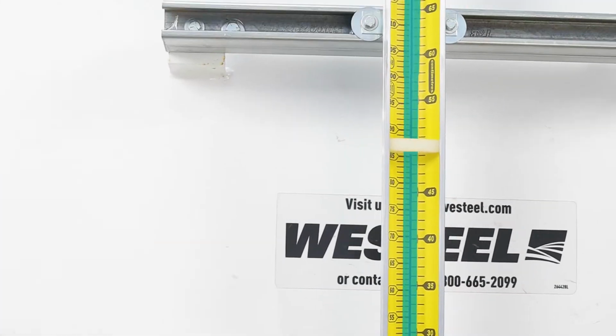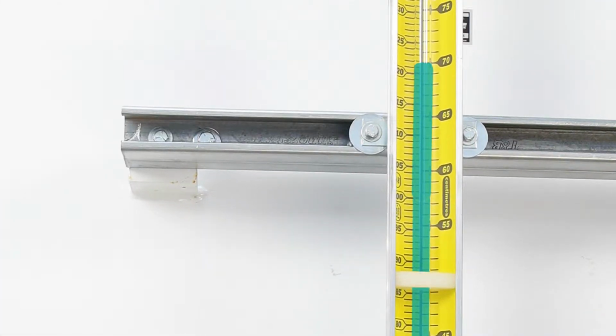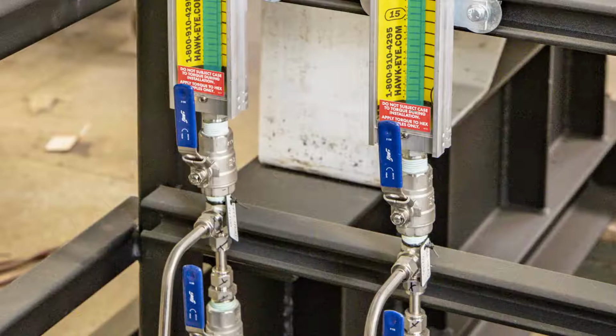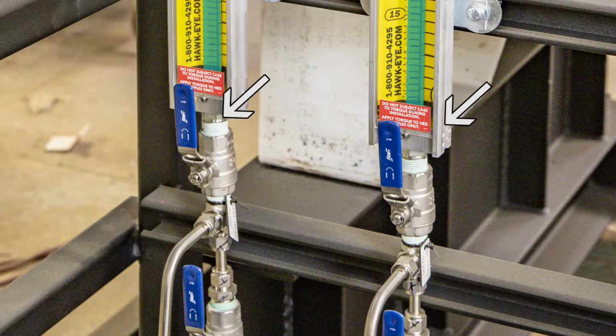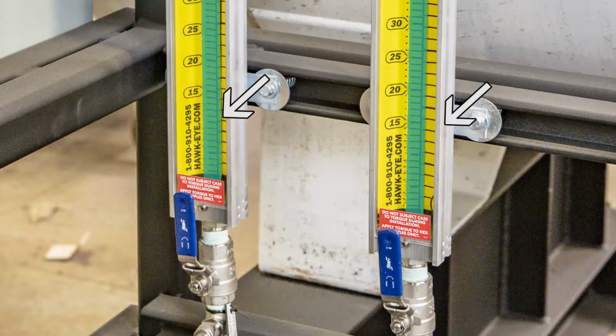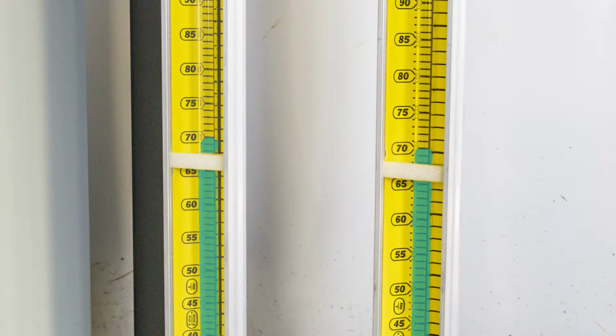Next, verify the supply tank has enough volume in it to fill the individual sight glasses for each chemical pump. Open the individual sight glass valves to allow the sight glasses to fill from the supply tank. Each division on the sight glass represents 1 liter per day being pumped. If you are pumping 30 liters per day, you'll require more than 30 divisions of liquid in the sight glass.